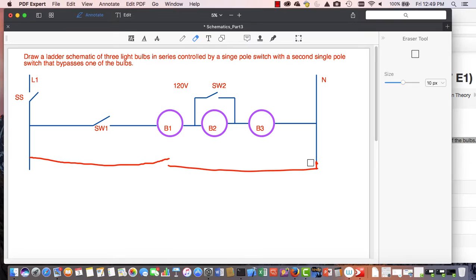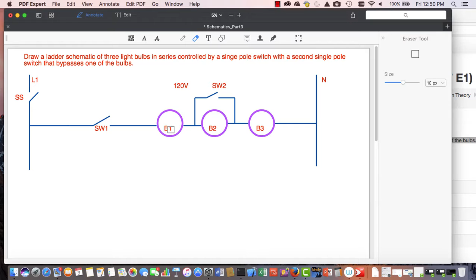So always make sure that every path of your circuit has a source, a path (which is my wire), a switch, and a load someplace along the way. Also, in HVAC, do not put any loads in series unless specifically told to. Most of HVAC uses switching devices in series, but not loads.